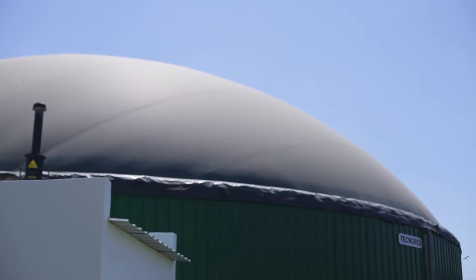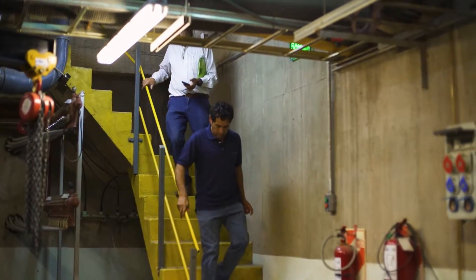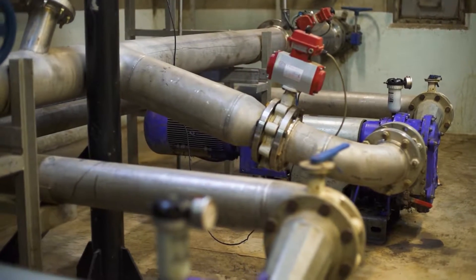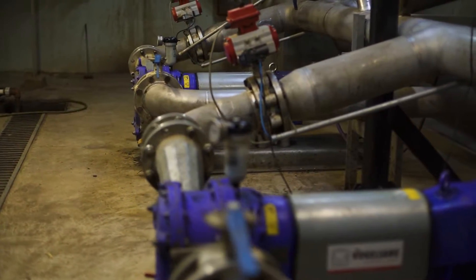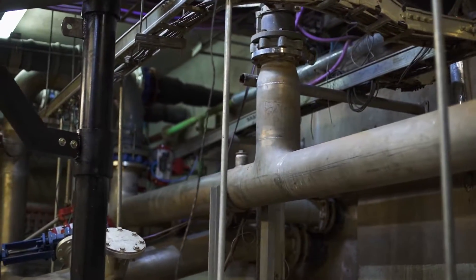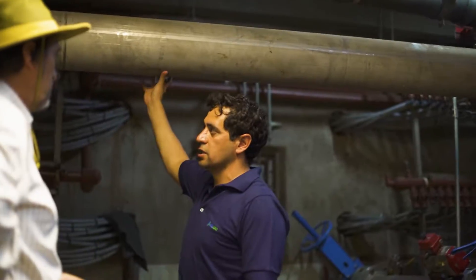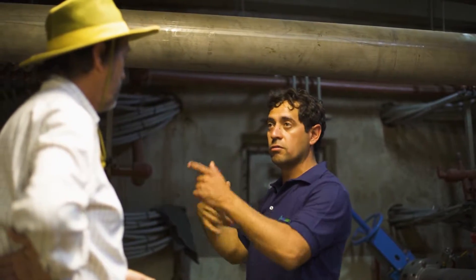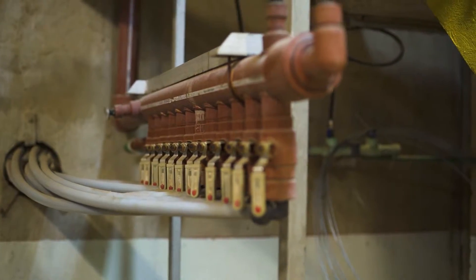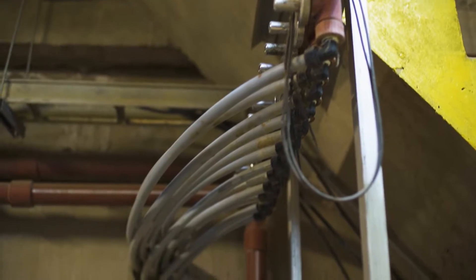The entire system is centralized in a special room where the different pipes converge underground. Load pumps drive all kinds of material. Pneumatic actuator valves and electric engines allow full control of loading, unloading, circulation and heating of the biogas. The concept of the plant is of a modular type, which allows exchange of content between all fermentation tanks, giving great plasticity and adaptability against changes in diet or failures in any of the fermentation tanks.